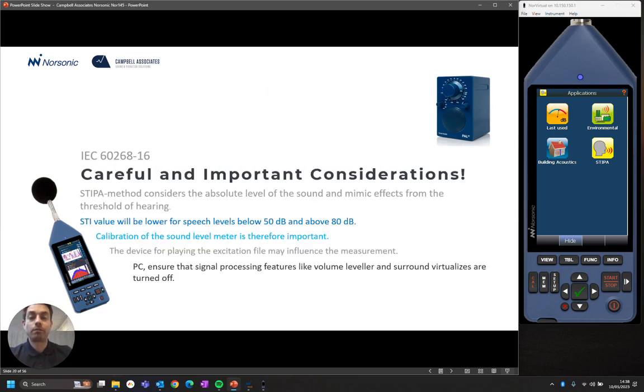So some careful considerations are that we need to be mindful that the value will be lower if the speech is below 50 dB or above 80 dB. There is a target level that I'll talk about shortly. The calibration of the equipment is very important, so we need to do this before and after the measurement. And we need to make sure that we have the right device for playing the sound back on. So if we're using a PC with a cable to a speaker, we need to ensure that the level is correct and that none of the equalization or virtualization or extra bass is on so that it influences the sound. We need to make sure that the sound is as flat as possible according to the standard.